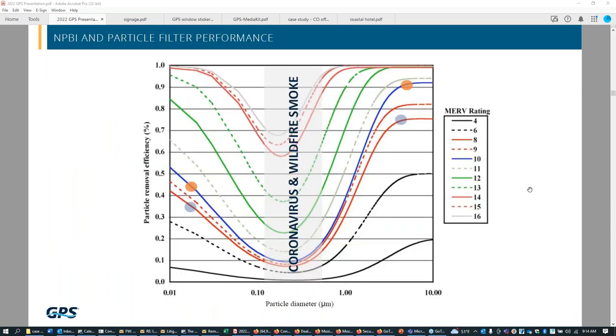So this chart comes from the filter industry and shows different MERV ratings and their particle removal efficiency at different particle sizes. The x-axis goes from 0 to 10 microns. And whether you have a MERV 8, MERV 10, or MERV 13 filter, all filters have a weakness in the 0.3 to 0.4 micron range. That is related to physics. We've got some appendix items that you can read about that explain why this phenomenon takes place.